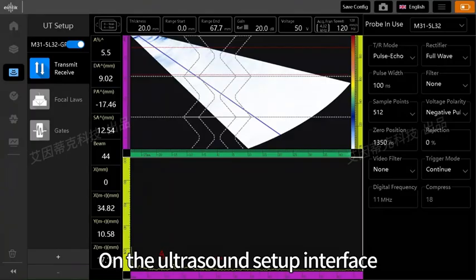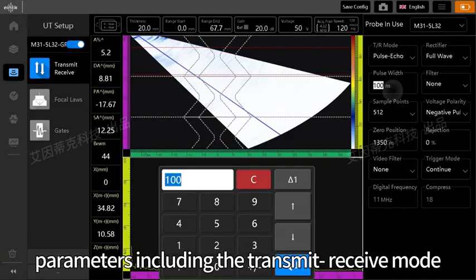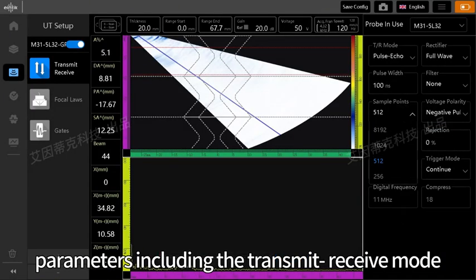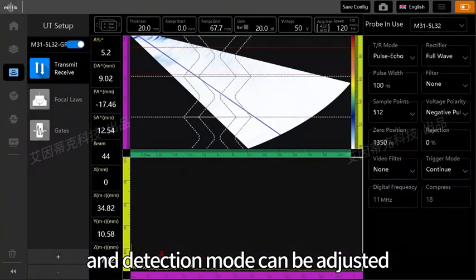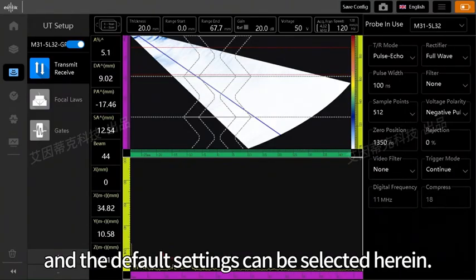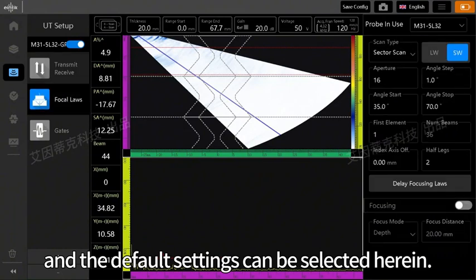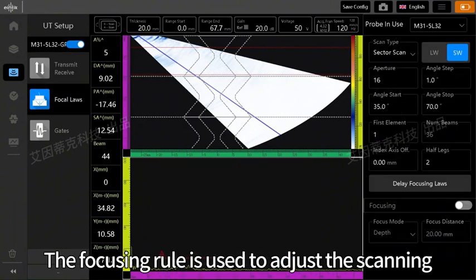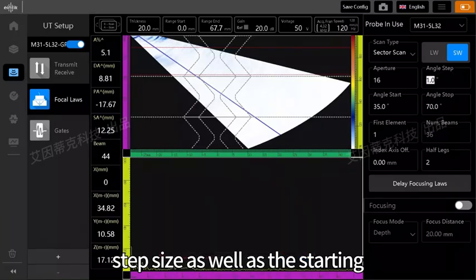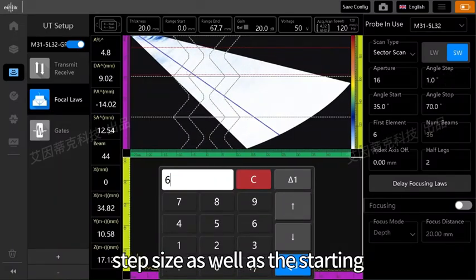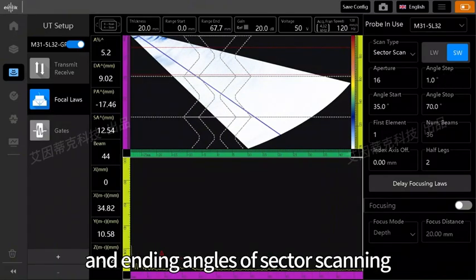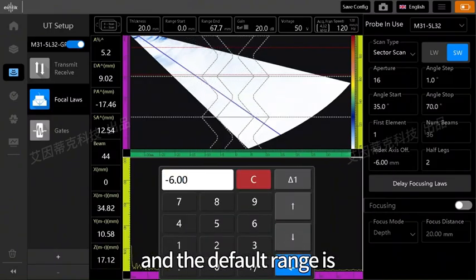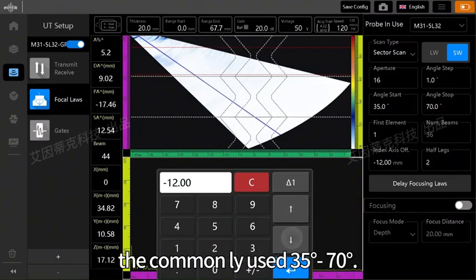On the ultrasound setup interface, parameters including the transmit-receive mode and detection mode can be adjusted, and the default settings can be selected here. The focusing rule is used to adjust the scanning step size as well as the starting and ending angles of sector scanning, and the default range is the commonly used 35 to 70 degrees.